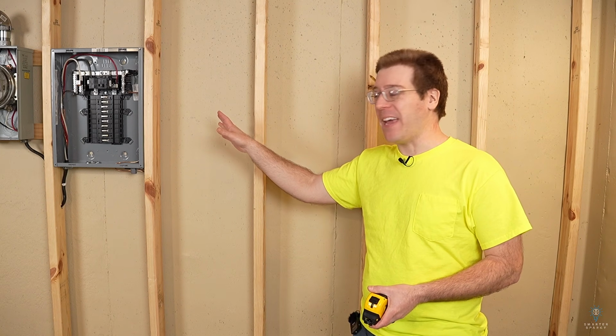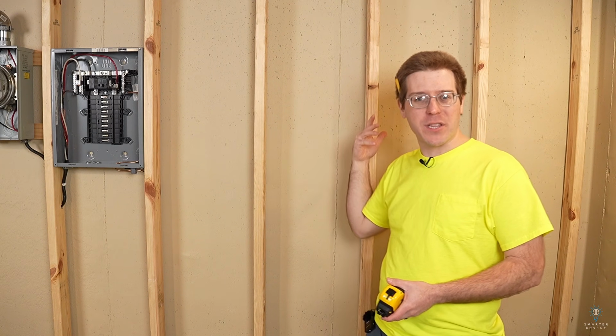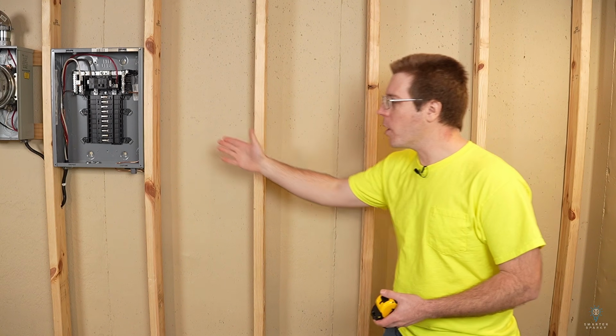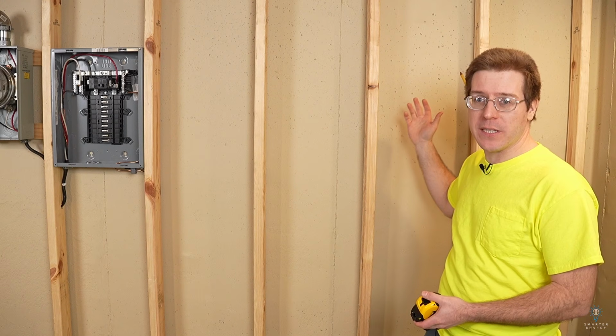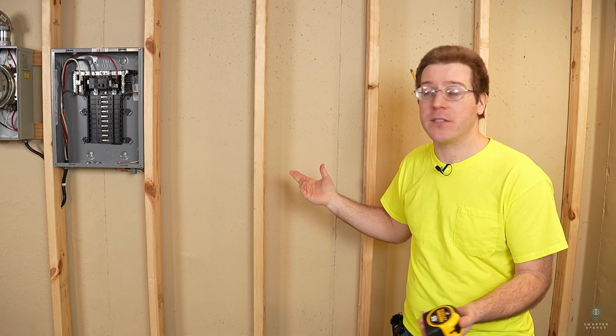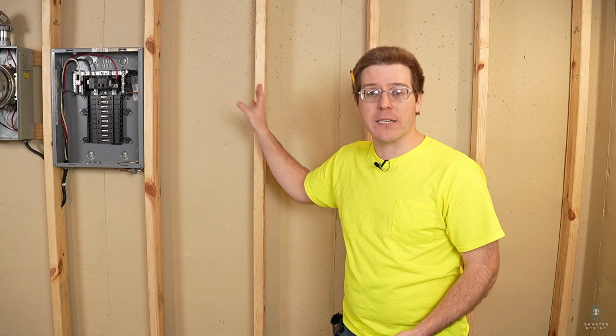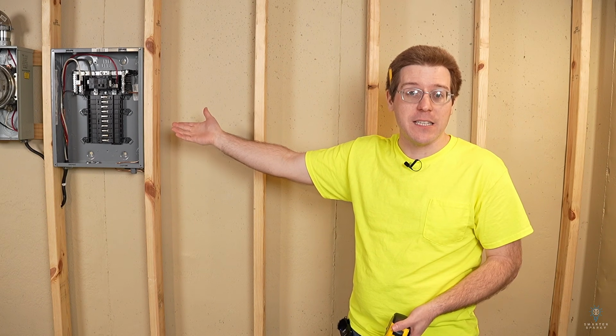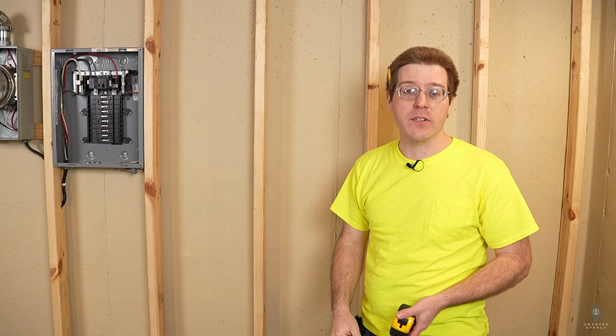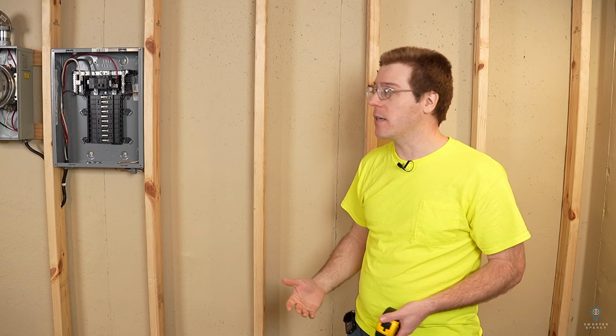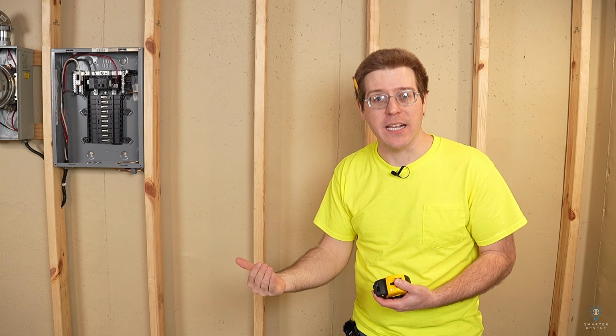Because I've already got a panel installed on this wall, I'm gonna match the heights of those 2 panels. We're gonna pretend that the distance here between these 2 panels is 100 feet. So maybe these panels aren't even in the same part of the building. They could be right next to each other. Maybe we ran out of space in this panel and we need to add another sub panel for that extra space. Either way, matching the heights of the panels is gonna add consistency to the installation.